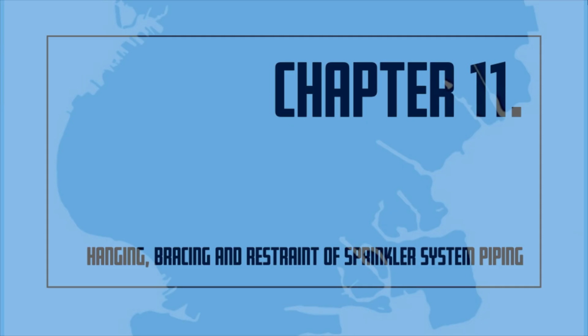piping. Unapproved or makeshift hangers, such as perforated strapping or baling wire, are prohibited. Nails shall not be used to fasten the system or building attachments to the structure. Hangers used with plastic piping must be listed for use with the piping material. A visual inspection of the system is performed from the floor to determine if the hangers, bracing, and restraints are in place and if the piping has moved from its original location and position. This can be observed if the hanger rods or piping attachments are not being supported adequately from the building, bent, misaligned, loose, or missing. Shifting of the system may occur during pressure surges, water hammering, alterations, testing, or operation.